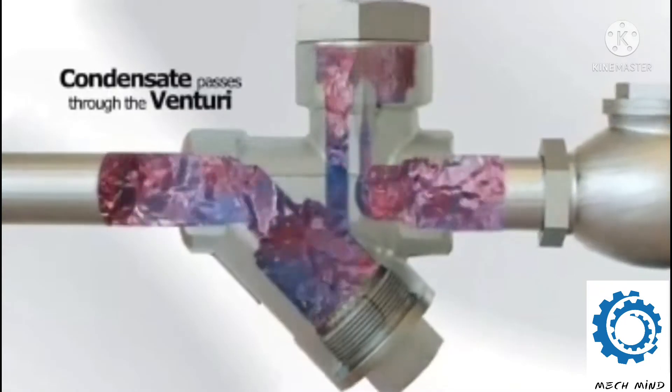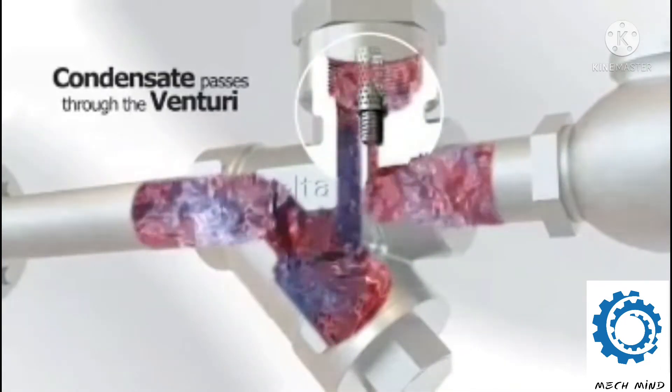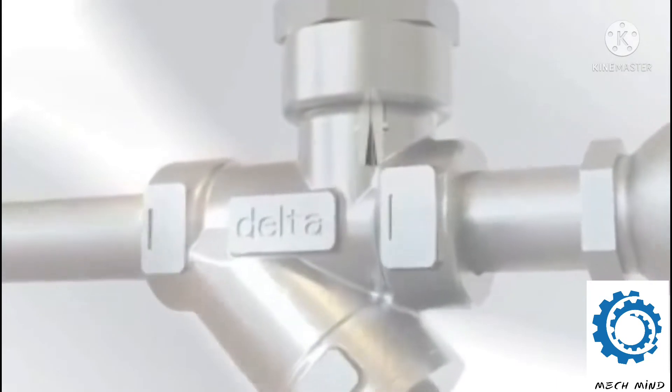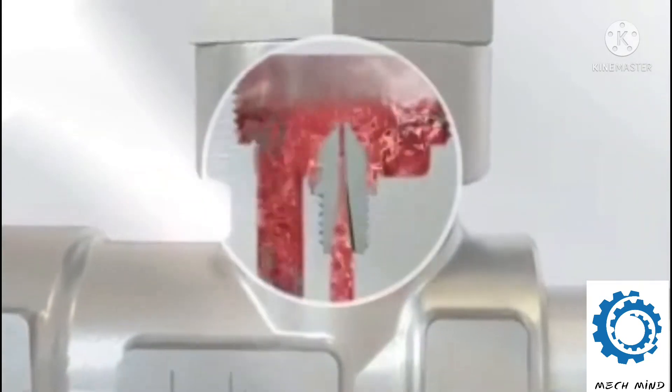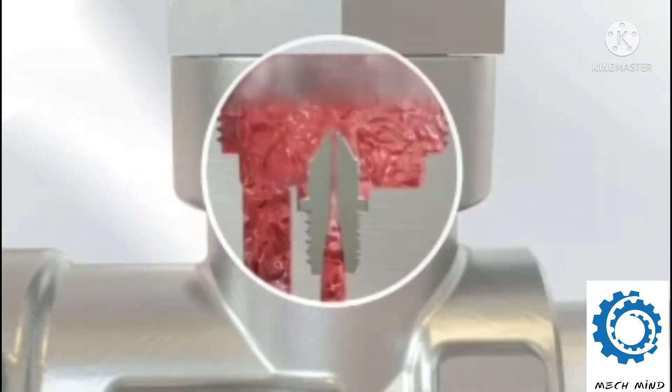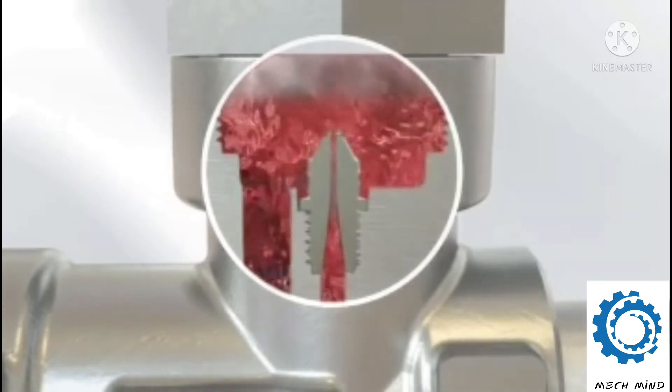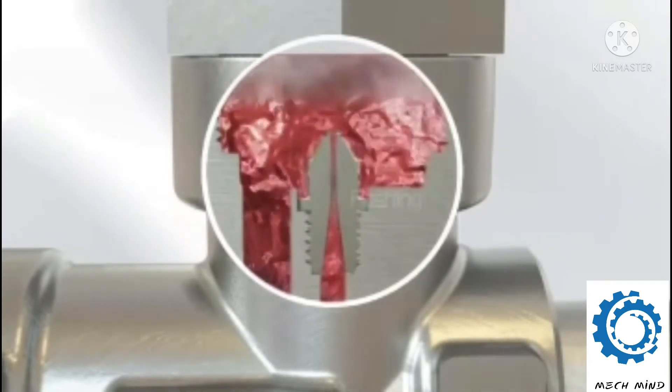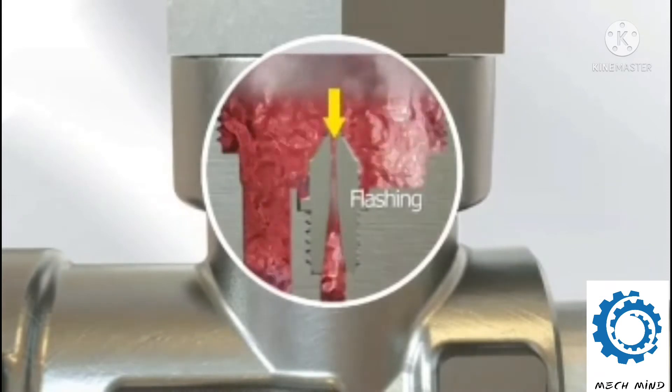This hot condensate passes through the orifice and enters the mouth of the venturi. As the condensate passes through the mouth of the venturi, there is a sudden pressure drop which causes a percentage of the hot condensate to change phase from condensate to steam, a phenomenon known as flashing.